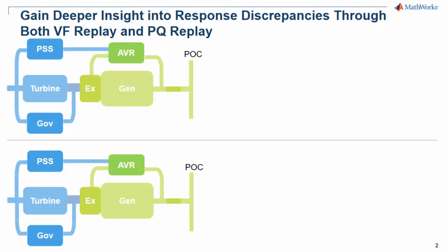For online performance monitoring, data replay involves exciting the plant model through physical measurements of voltage or current at the grid point of connection. It's common to consider voltage, frequency, active power, and reactive power as the four measurements necessary to perform power plant model validation.